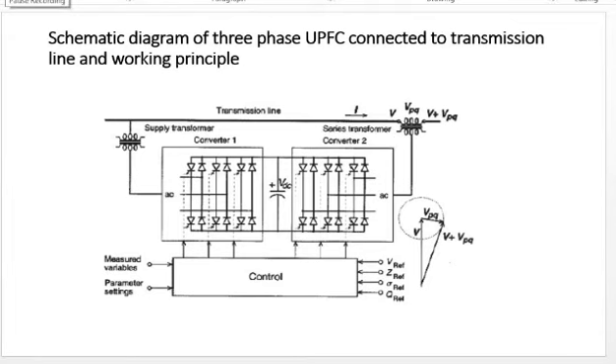The series voltage source converter provides the main function of the UPFC by injecting a voltage with controllable magnitude and phase angle in series with the line through the injection transformer. This injected voltage acts as a synchronous AC voltage source. The transmission line current flows through this voltage source, resulting in reactive and active power exchange between it and the AC system.